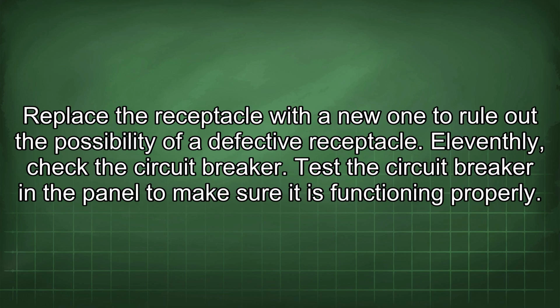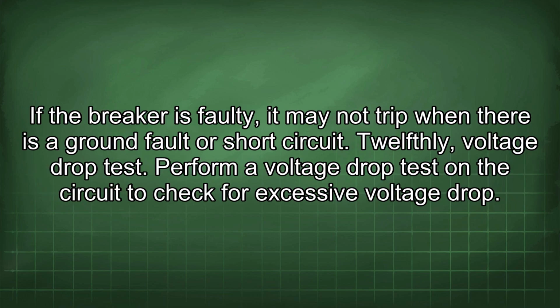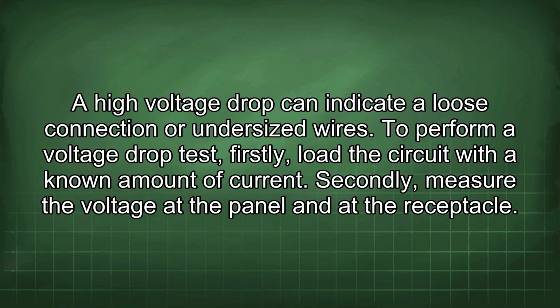Tenthly, test the receptacle. Replace the receptacle with a new one to rule out the possibility of a defective receptacle. 11th, check the circuit breaker. Test the circuit breaker in the panel to make sure it is functioning properly. If the breaker is faulty, it may not trip when there is a ground fault or short circuit. 12th, voltage drop test. Perform a voltage drop test on the circuit to check for excessive voltage drop. A high voltage drop can indicate a loose connection or undersized wires.